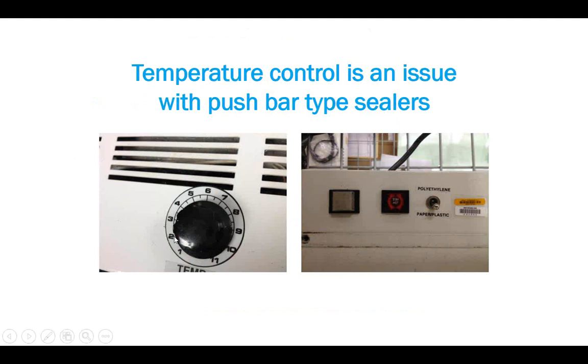Here's what happens on many of these sealers: people just turn a number, and some old ones just click a switch. You need to verify you have the correct seal temperature, because many different companies' pouches can cause a problem. If you're on setting 7, what is the real temperature? If it's not sealing, you might go up to 7.5, maybe 8, maybe 9. As you turn it up, you start burning the film and causing problems with the seal itself.